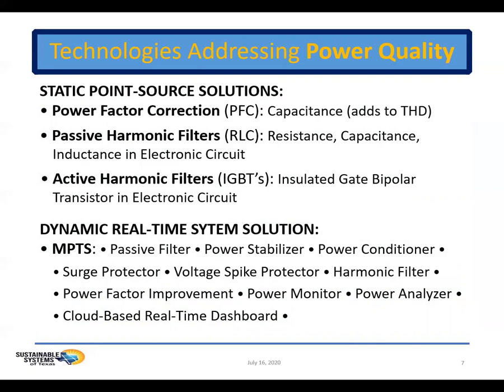Thanks, Michael. Let's talk about the current technologies that address power quality. Today, power quality problems are addressed by many older technologies. As an example, devices that provide power factor correction are really capacitance that actually adds THD, total harmonic distortion, to the system. Capacitors correct the power factor. They do not improve or eliminate harmonics problems in a system. Capacitors actually add to the harmonics in a system.